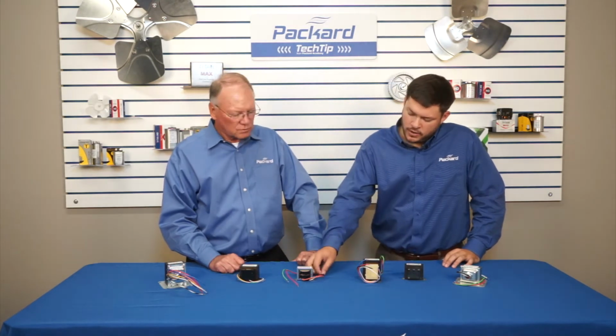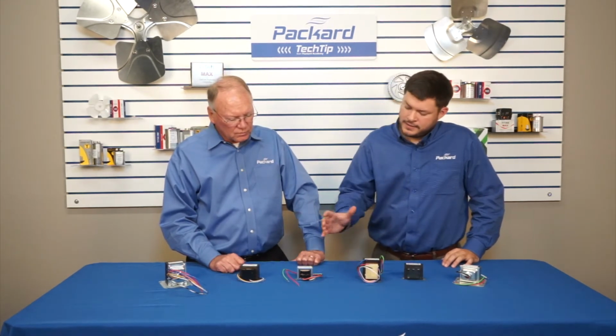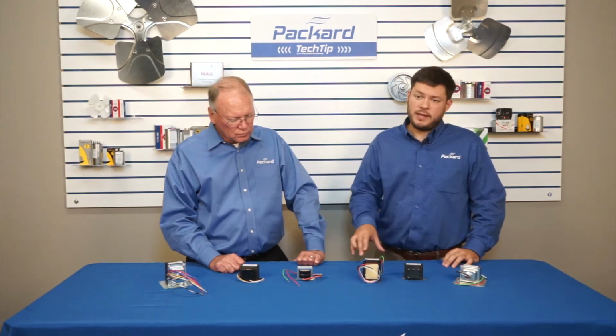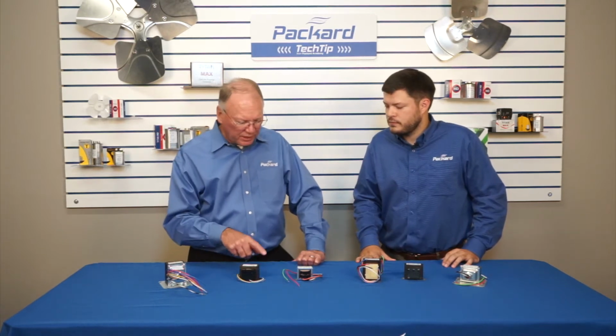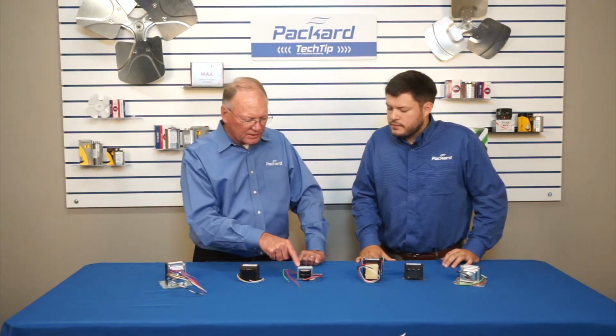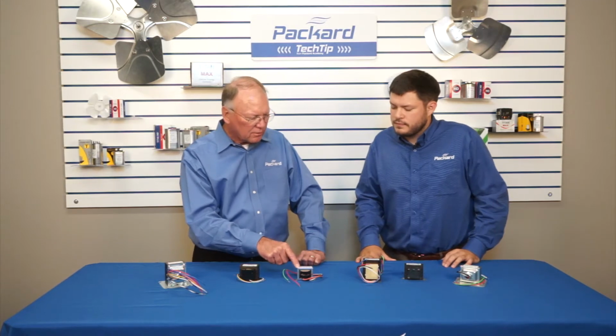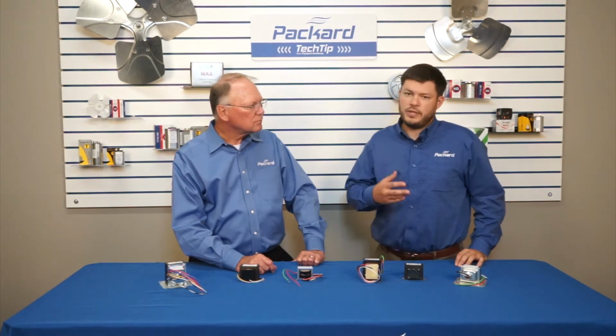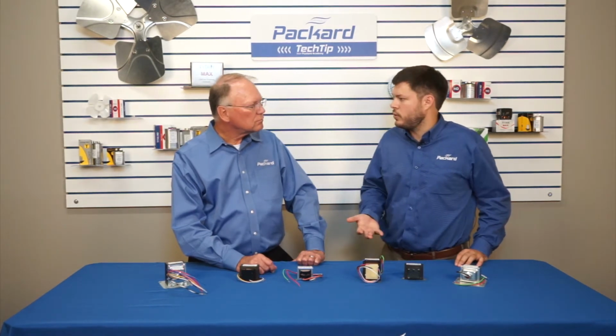Each pair of leads is associated with one voltage or another on your primary side as well as your secondary side. Now I see that on here and I see this PRI and I see SEC. What are those? PRI is going to be your primary side, which is your source voltage. SEC is going to be your secondary side. That's your reduced voltage that's going to go to typically a switch or controller of some sort.